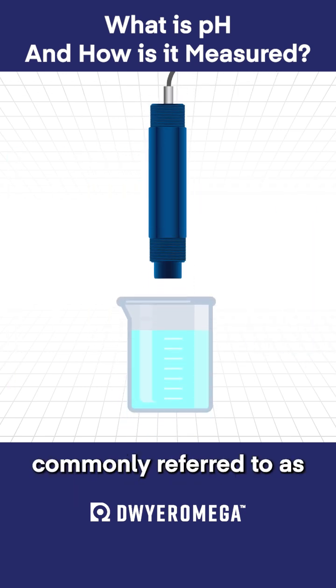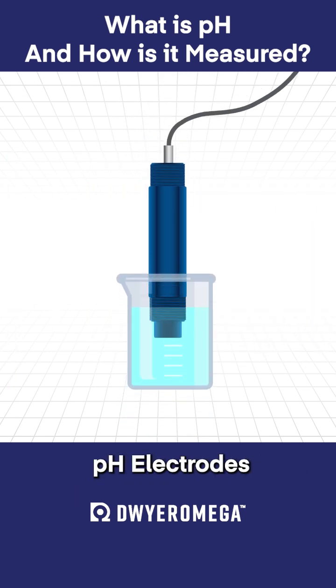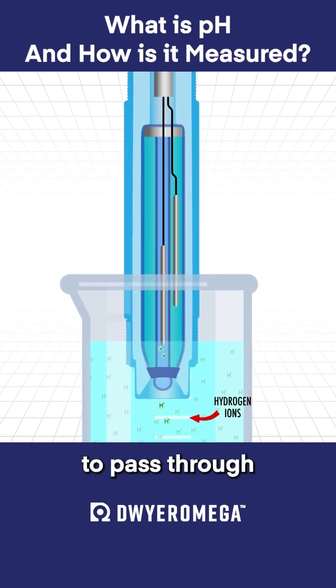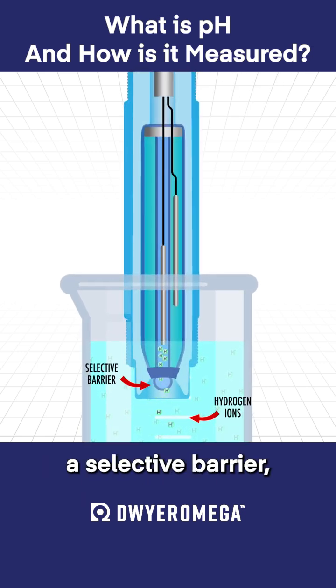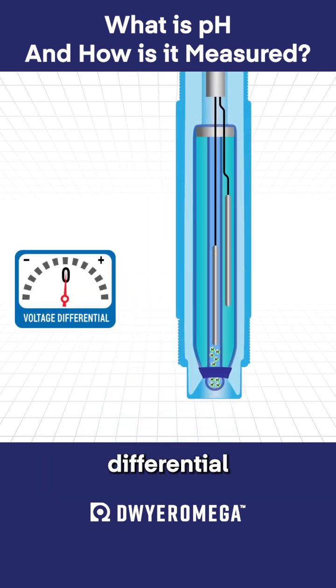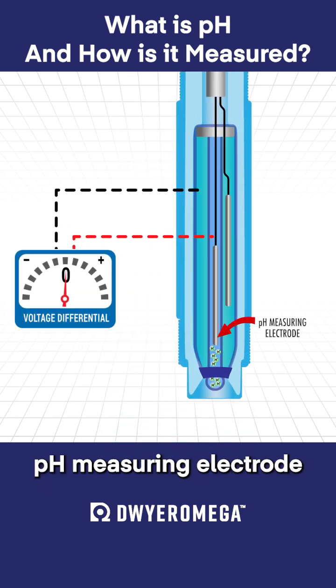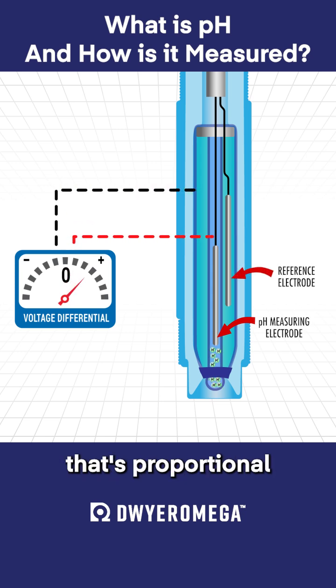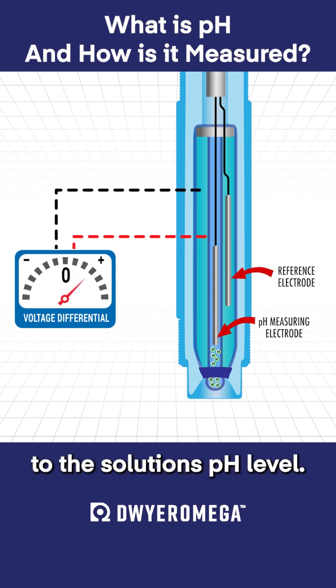pH sensors, commonly referred to as pH electrodes, are designed to allow hydrogen ions in the solution to pass through a selective barrier, generating a measurable voltage differential between the pH-measuring electrode and the reference electrode that's proportional to the solution's pH level.